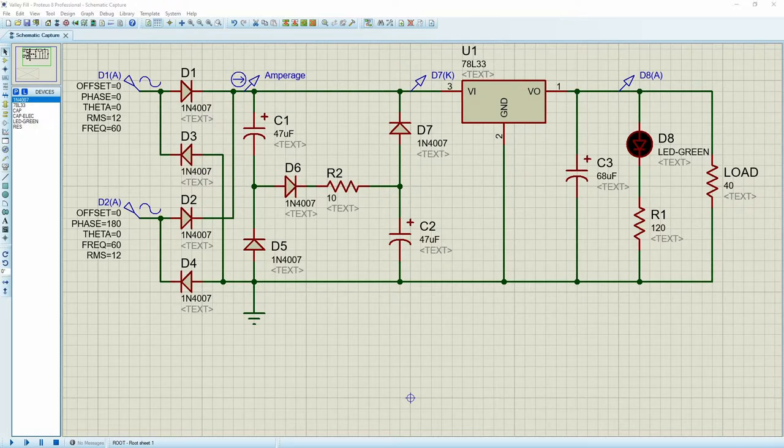So as LED lights have become more and more prevalent, one of the issues has become that we have an issue with capacitance on our AC circuits. In the old days, we had a lot of inductive loads, and they caused one problem. And the problem is that as you introduce capacitance or inductance into an AC circuit, you start to shift the current out of phase with the voltage. And so large industrial applications would have these huge motors that would actually shift the current out of phase with the voltage, and you would have problems with transformers and transmission lines, and more importantly, the billing.